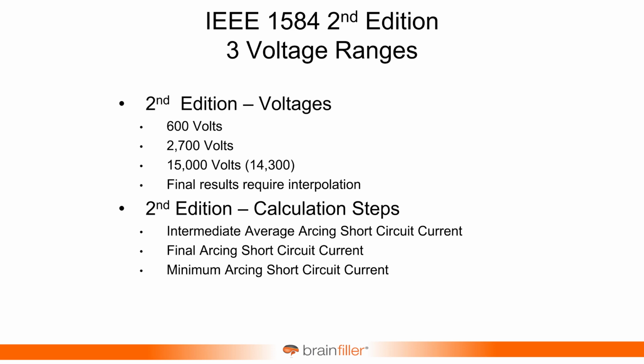So you begin with the intermediate. That's the initial. That's going to be at 600 volts or 2700 or 14.3. And once you go through that, and you go through all the other calculations for the arc flash boundary, incident energy, then you go back and there's the adjustment factor. Now in the 2002 it was the 85% adjustment factor. Here it's adjusting for the minimum current. As I said, it goes from 208 all the way to 15 kV. So you make your adjustments for the minimum current, and then what you do is you take this minimum current, kind of like the 85% that we had. You look at this minimum arcing current and you evaluate the time current characteristic and determine, well, did the clearing time change? By using the minimum current, did that maybe drop below an instantaneous setting? And now we have a time delay. So it's similar to what we had with the 85% multiplier back in 2002. Well, it came out in 2004 with the amendment.